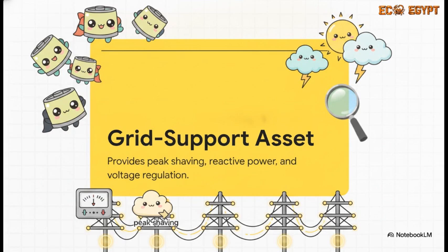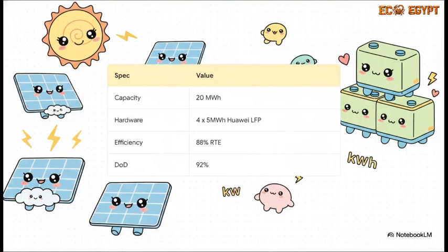As a bonus, during construction and operation this same system can supply temporary site loads and EV charging infrastructure. To pull that off we rely on heavy-duty specs: a 20 megawatt-hour lithium iron phosphate, or LFP, battery paired with a massive 45 MVA bidirectional power conversion system. Using an AC-coupled topology with staged augmentation and full EMS, BMS, and SCADA integration, this setup smoothly delivers vital output exactly when the grid demands it.